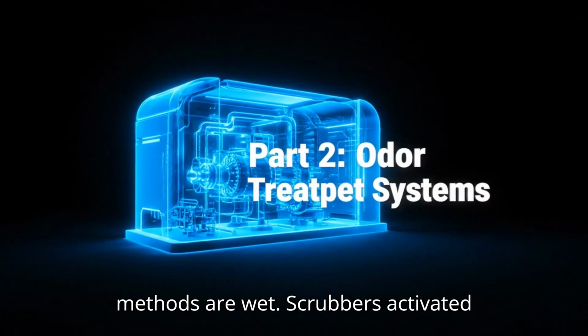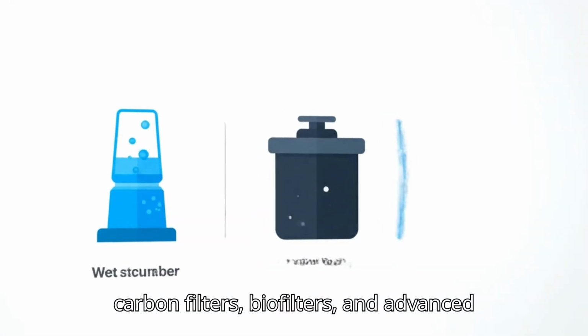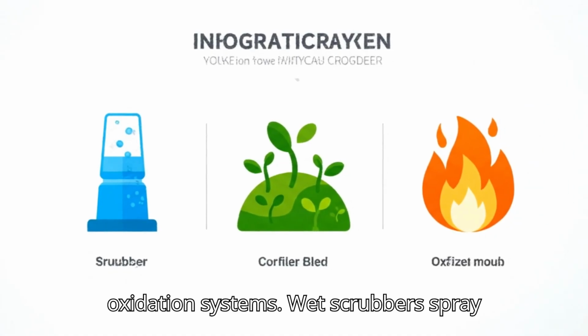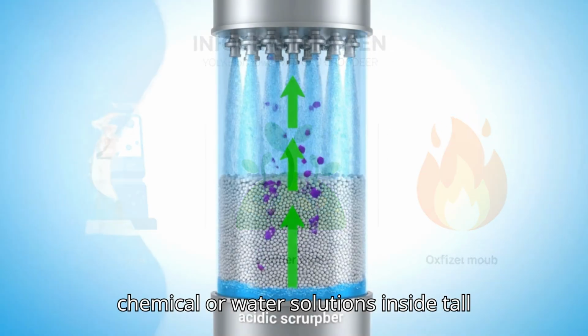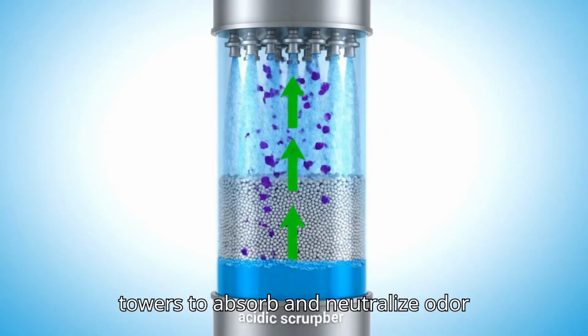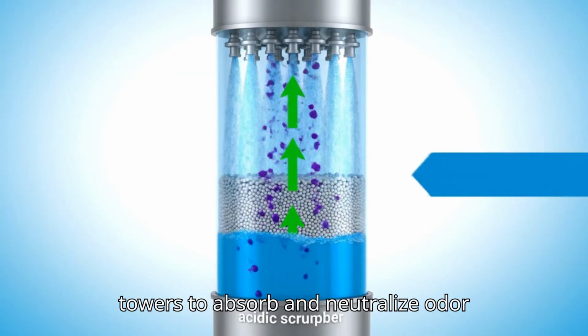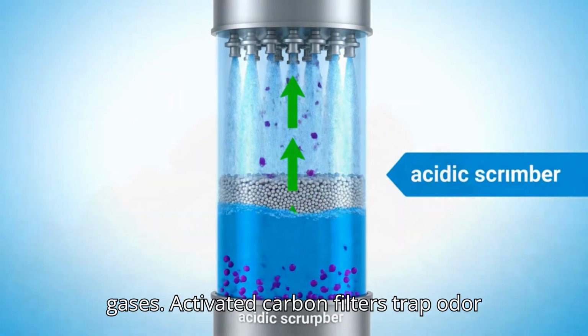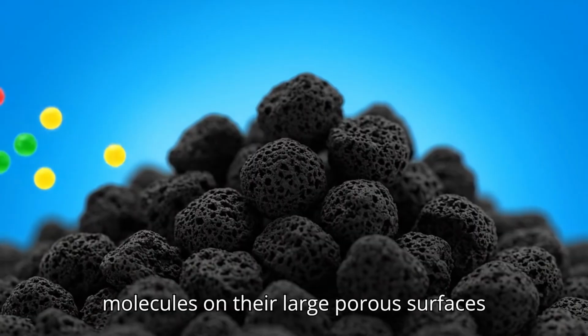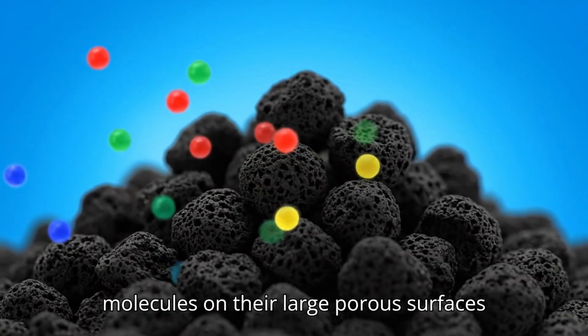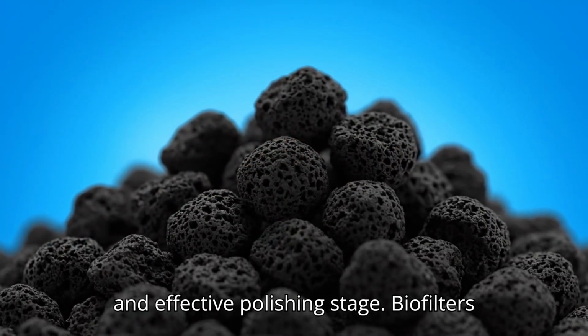The main odor treatment methods are wet scrubbers, activated carbon filters, biofilters, and advanced oxidation systems. Wet scrubbers spray chemical or water solutions inside tall towers to absorb and neutralize odor gases. Activated carbon filters trap odor molecules on their large, porous surfaces, an effective polishing stage.